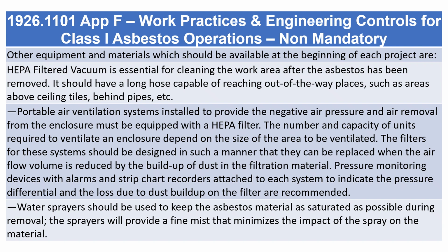The number and capacity of units required to ventilate an enclosure depend on the size of the area to be ventilated. The filters for these systems should be designed in such a manner that they can be replaced when the airflow volume is reduced by the buildup of dust in the filtration material. Pressure monitoring devices with alarms and strip chart recorders attached to each system to indicate the pressure differential and the loss due to dust buildup on the filter are recommended.